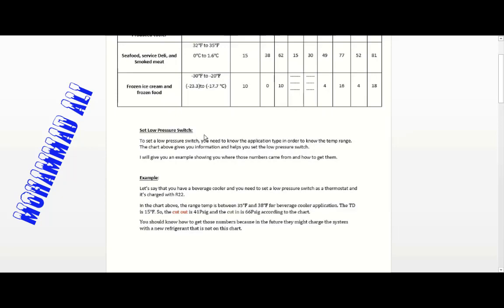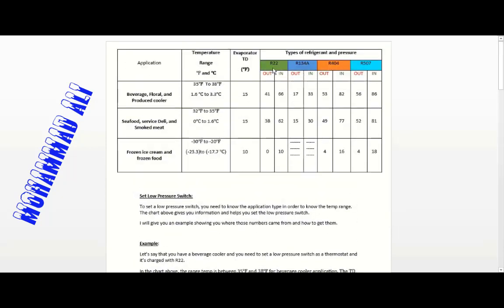Here I have R22 as an example, with the application of cooling beverages. To cool beverages, we set the temperature between 35°F and 38°F (1.6°C to 3.3°C), with a TD of 15. For R22, the cut-out is 41 PSI and the cut-in is 66 PSI, so you can simply follow the chart to find those values.